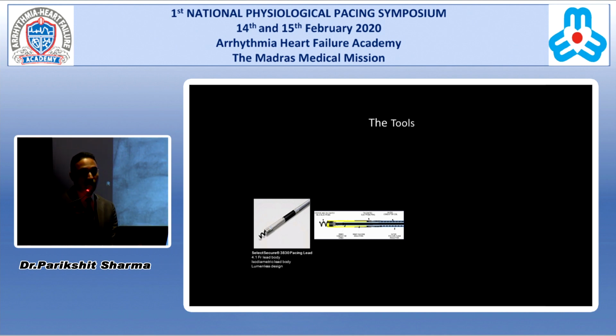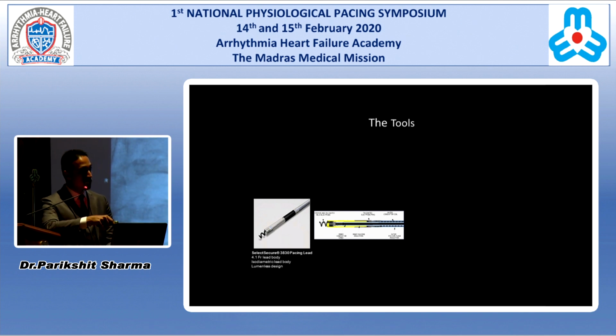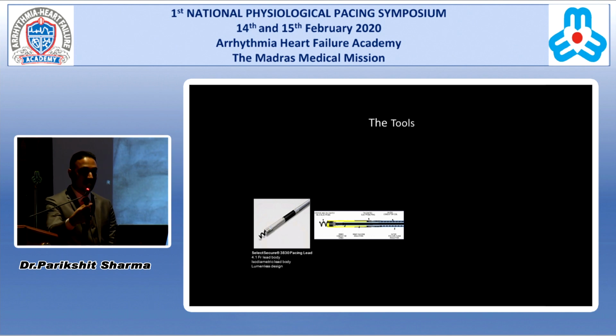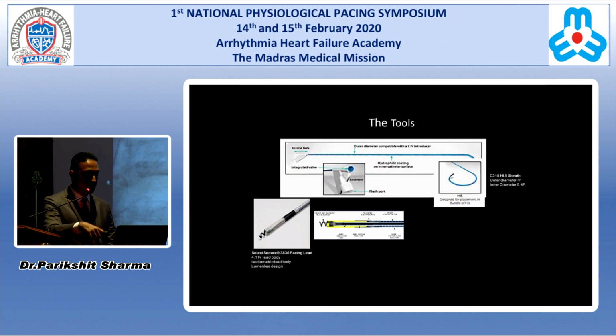And because it's lumenless, it requires a delivery sheath. The other thing with this lead is that it has an exposed helix. So it is not extendable, retractable, it's an exposed helix. And so you have to rotate the lead body to get a bite into the conduction system. The delivery sheath that you are all hopefully familiar with is the C315. It has two curves. The primary curve, which is septal, and the secondary curve, which points it towards the RV.